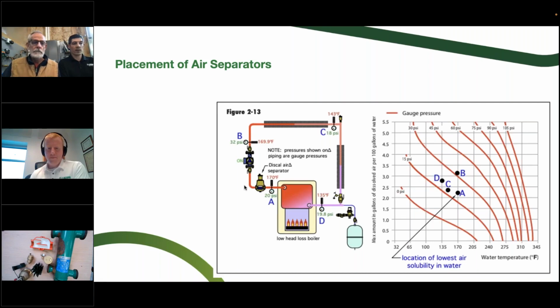So one of the things that comes up with this is, let's say it's a modulating condensing boiler like the one behind us, and you commission on a day in April. And it's kind of warm out, so the outdoor reset curve had a maximum supply temperature of 105 degrees Fahrenheit or something like that. You could still walk out that boiler with air later in the year, let's say on New Year's Eve, because now you're at a much higher temperature and you've had more air come out of solution. So you could have purged that bulk air really well, the entrained air you could have gotten out really well, but you have hidden air left that you have to get out when it's at a high temperature. So one way to do that in the summer would be to get it up to the top of your outdoor reset curve.